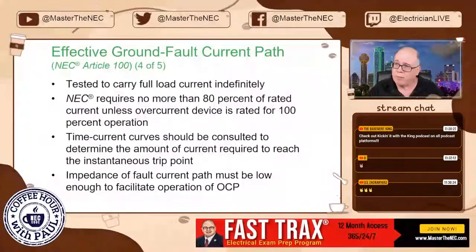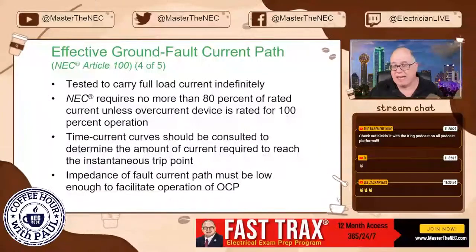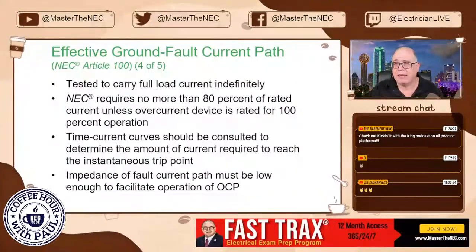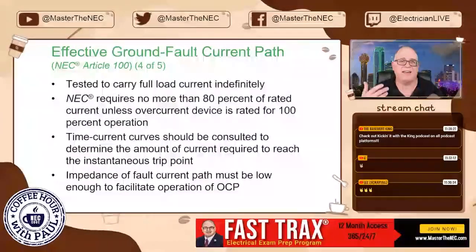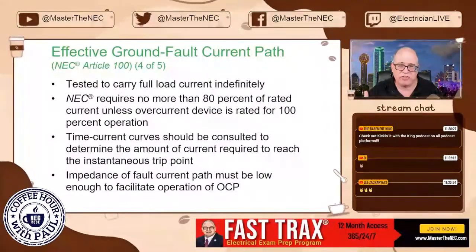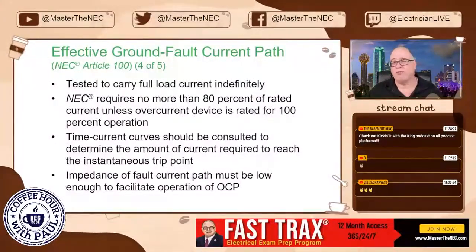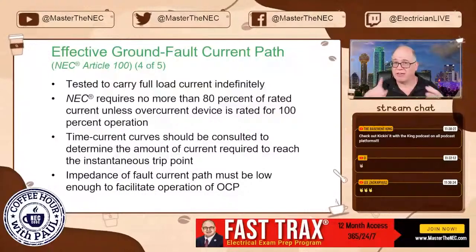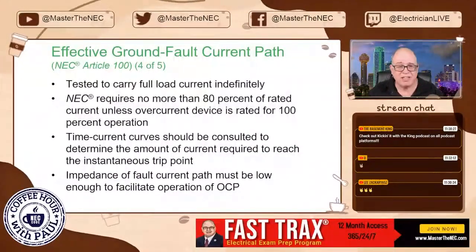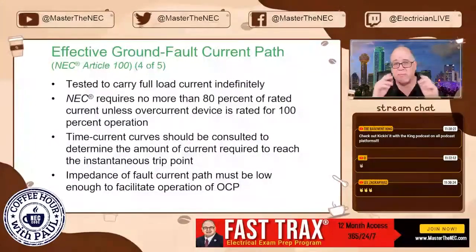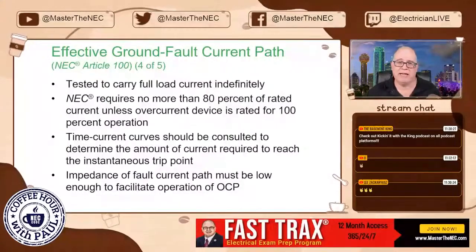EMT. When people say, can I use EMT as an effective ground fault current path? The answer is absolutely. The Steel Tube Institute made sure that all those manufacturers had testing, and the Gemini project at Georgia Tech was done years ago. It provides a very good effective ground fault current path as long as your connections are done right. If you have a conductor run and you size it right, you still have to make good connections. But you have many ways to do that.